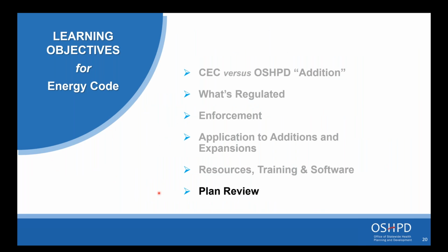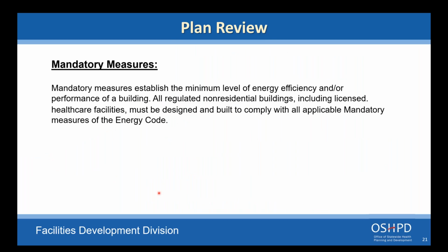So we'll look at OSHPD plan review requirements. The energy code has mandatory requirements. Mandatory measures establish a minimum level of energy efficiency and/or performance of the building. Healthcare facilities must meet these mandatory requirements. It should be mentioned though that there are several exemptions of mandatory requirements required for other facilities, and healthcare has been exempted from them. An example is the solar requirements for buildings—healthcare is not required to meet these requirements.